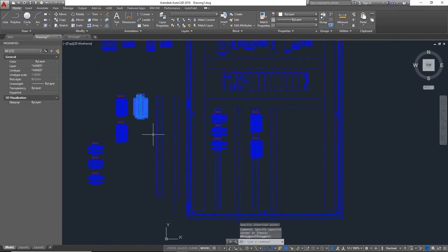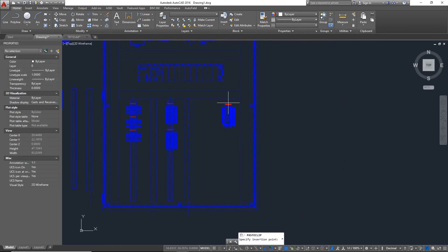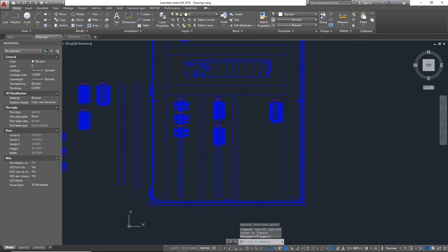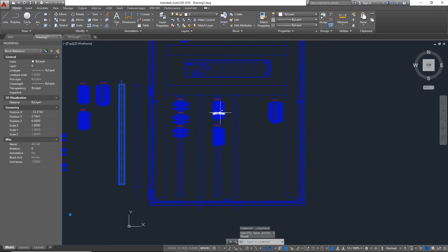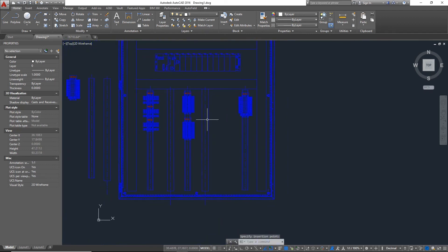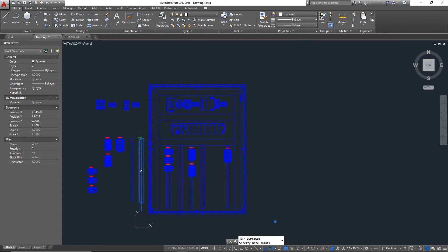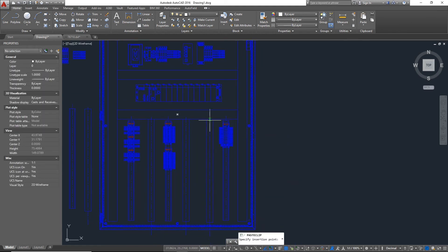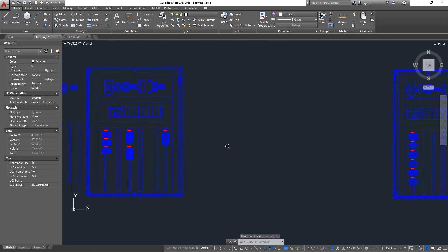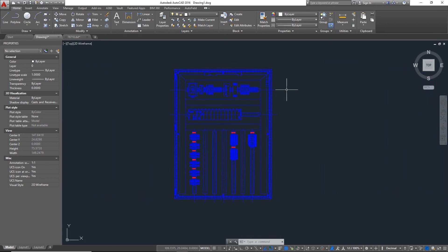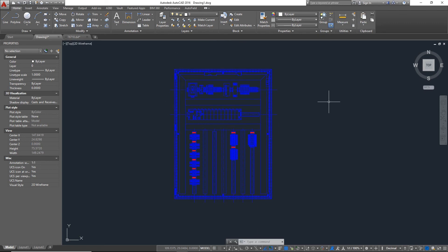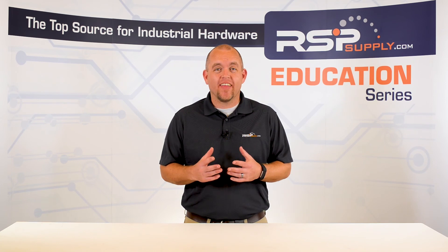Remember that this is the final design phase. We want to make sure that everything we do here is going to fit properly — that we have the right spacing between terminal blocks and enough room for wires to run through the different sections of wire ducting. You can see we're starting to get a very complete picture of what this design is actually going to look like. At this point it's a matter of fine tuning and making sure things are placed where we want them. Skipping ahead to what a final design looks like: all the power distribution hardware is placed with the right amounts, the PLC, all the IO hardware, and a very complete design including lights and enclosure. This is what you want your final design layout to look like, and at this point you're ready to move on to the next step.